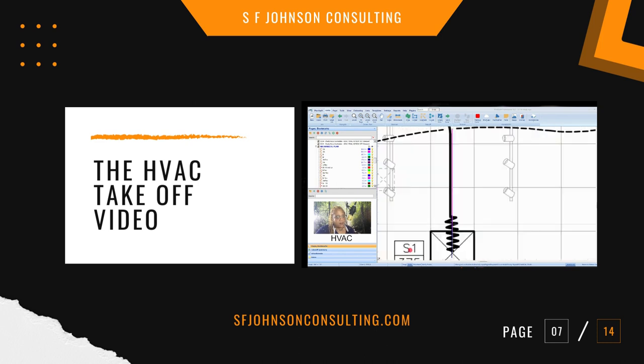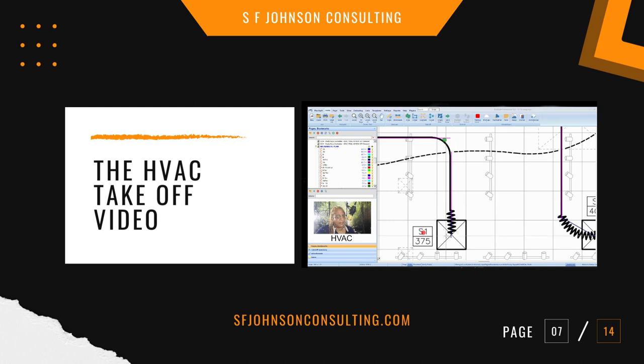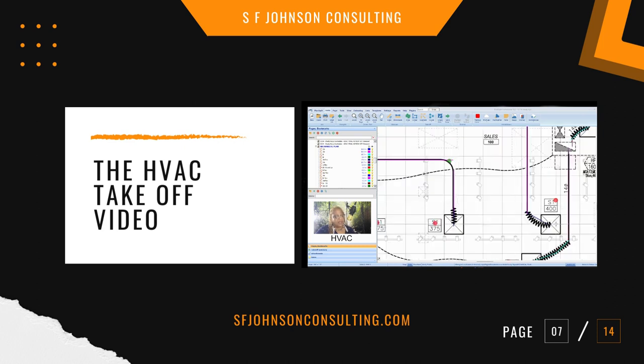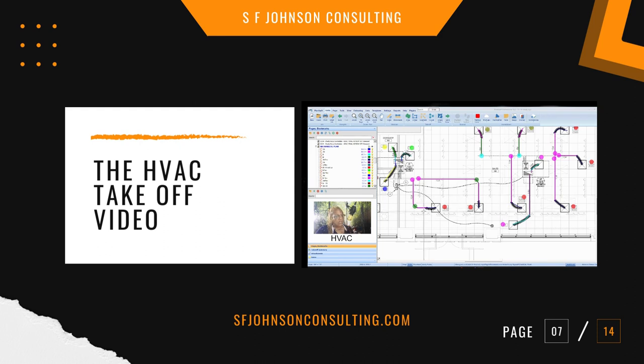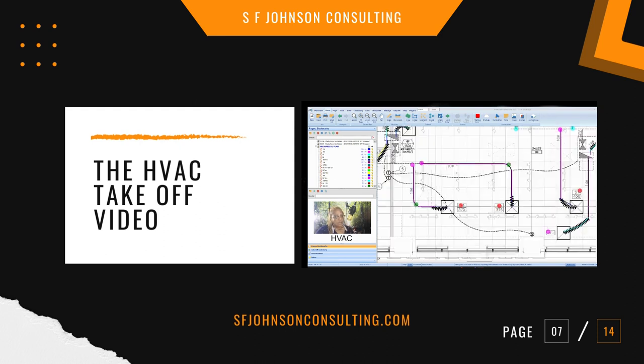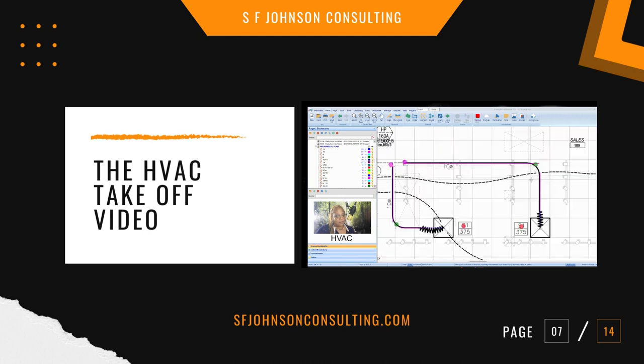And then they're also showing us our flex ductwork, and so I just measured that out. And here from the details, it's just the flex ductwork connected directly to the supply grills. But what you have to make sure you do is each of the supply grills are broken down based on the size of the neck. So the neck size here is going to go with the size of the ductwork. So that's going to be a 10-inch neck size 2x2 supply grill.